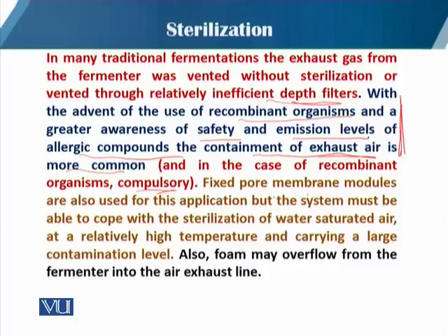The fixed pore membrane modules are also used for this application. But the system must be able to cope with the sterilization of water saturated air. As I have already told you, the exhaust air has a saturated water content, at relatively high temperature, and carries a large contamination level. Also, foam may overflow from the fermenter into the exhaust air. So these are very real limitations when we are selecting the sterilization process for the exhaust air.